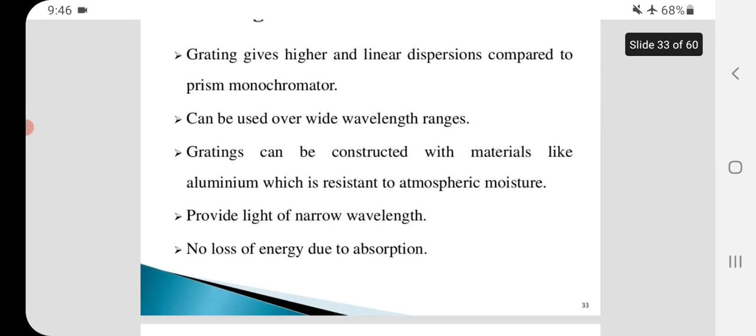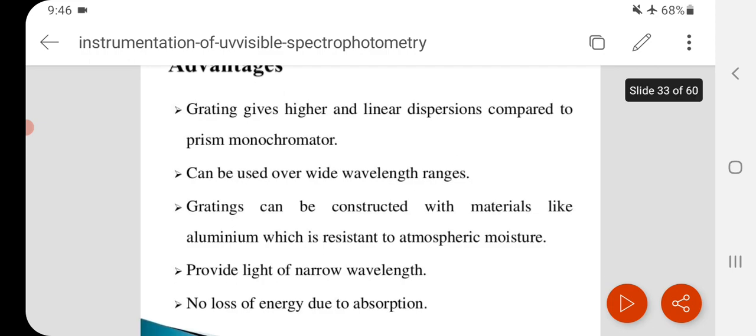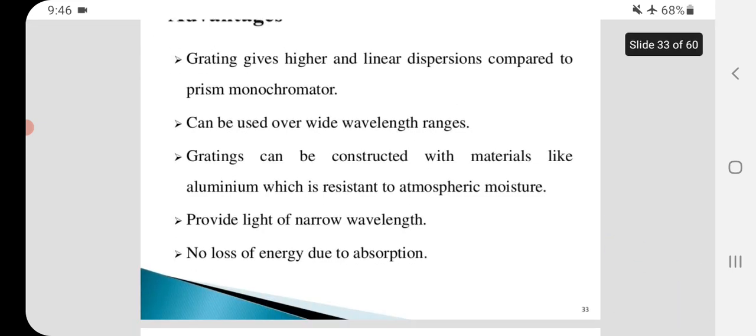Advantages: Grating gives higher and linear dispersions compared to prism monochromator. Can be used over wide wavelength ranges. Gratings can be constructed with materials like aluminum which is resistant to atmospheric moisture. Provide light of narrow wavelength. No loss of energy due to absorption.